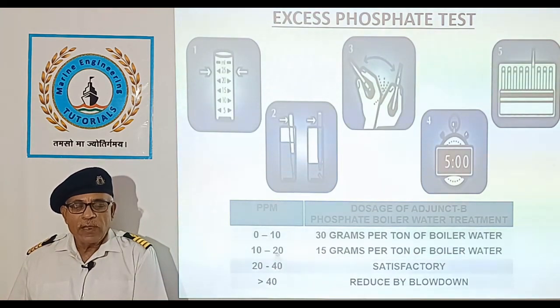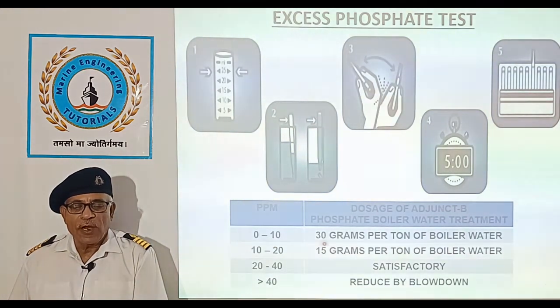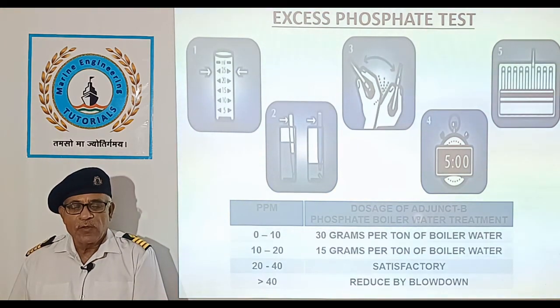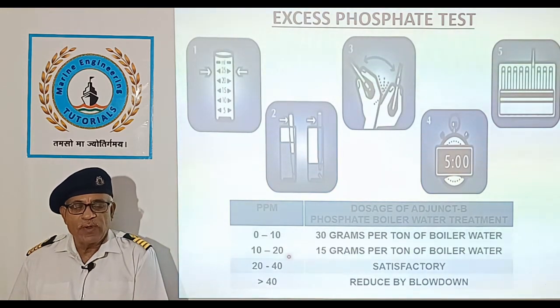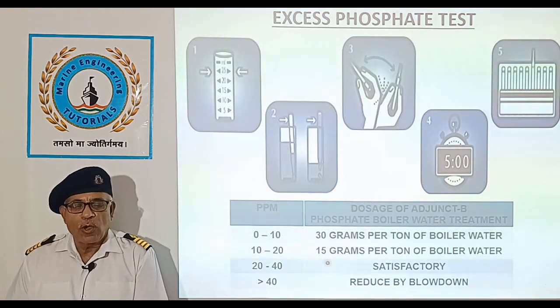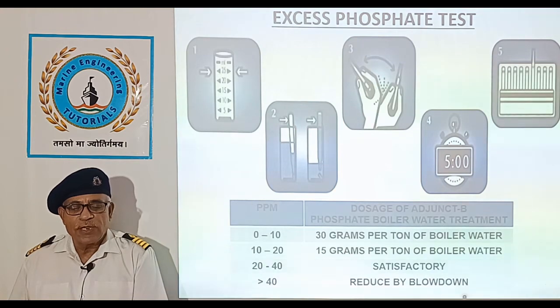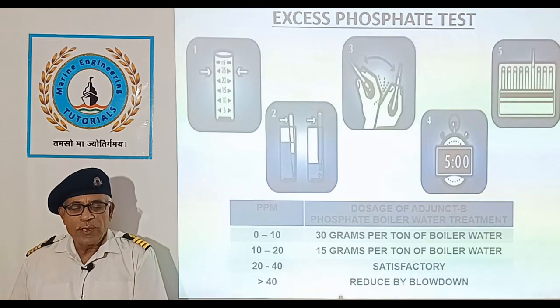If the value of excess phosphates is between 0 to 10 ppm, we need to add 30 grams per ton of boiler water. Between 10 to 20 ppm, we need to add 15 grams per ton of boiler water. Within 20 to 40 ppm, it is the satisfactory range. But if it exceeds 40 ppm, we need to reduce it by blowdown.